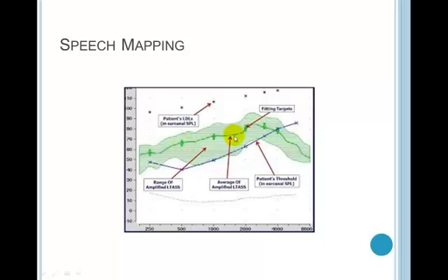Okay, and we can set targets for how loud soft speech should be, moderate speech, loud speech. So as the story is running, we can say, oh, all right, across the frequency range, we're really hitting where we should. Or if we're not, we can say, oh, okay, no wonder you're having difficulty, or it's not clear, or it's tinny, and we know exactly where to make adjustments. Okay, so this is fitting to target.